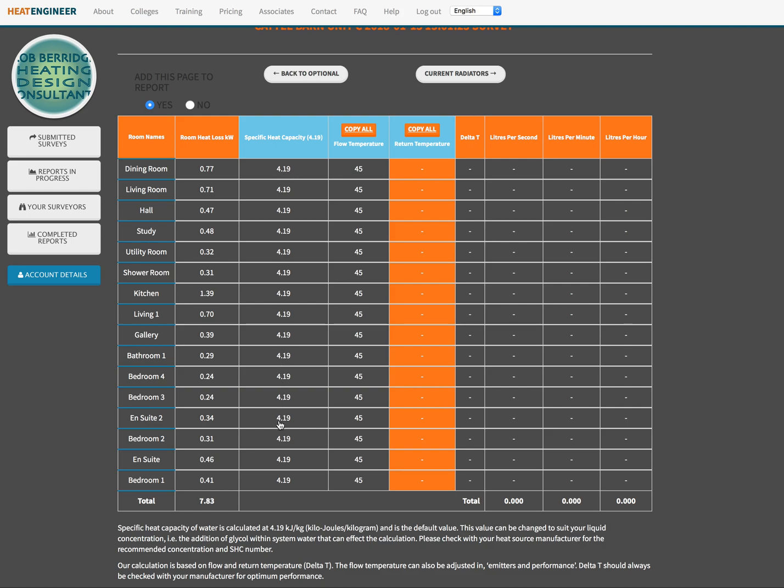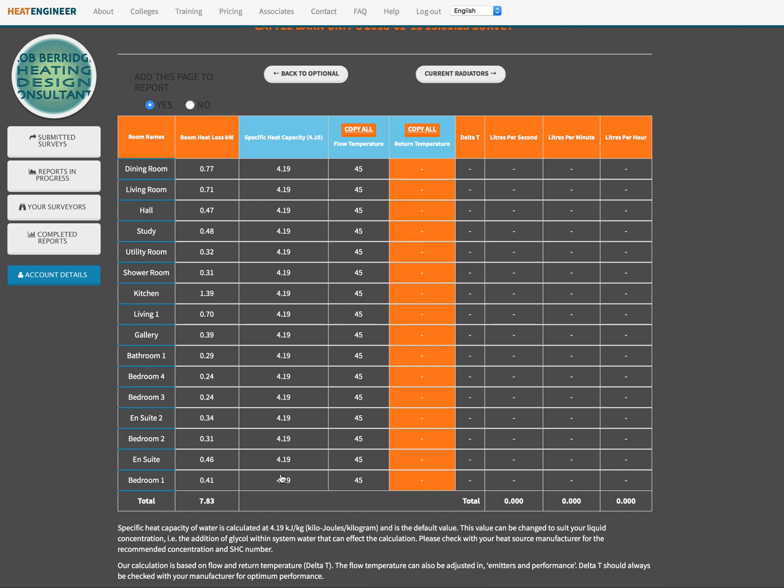This would normally be the situation for any products that don't have units outside or prone to freezing. As we know with new technology that's coming on, quite a lot of systems now, certainly with renewable systems, will have some form of glycol mix within the system. Glycol adding to water can change the specific heat capacity of that water. So what we suggest that you do is you speak to the manufacturer of the heat source, find out what the percentage of glycol mix is that's required to go into the system.